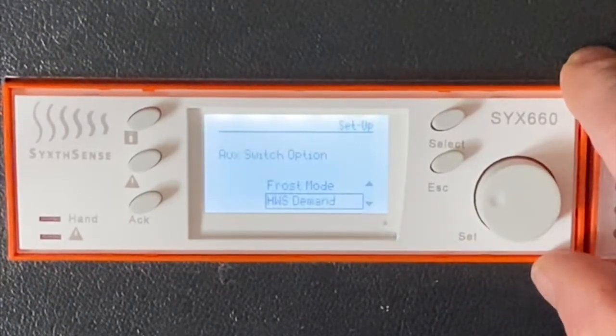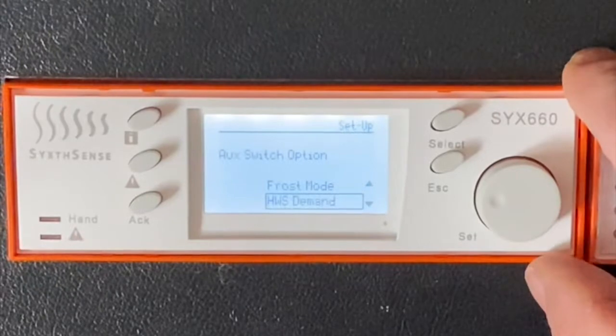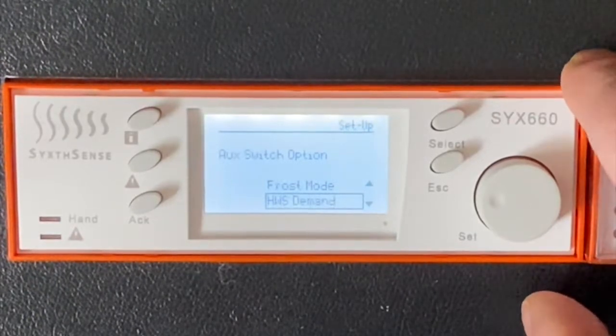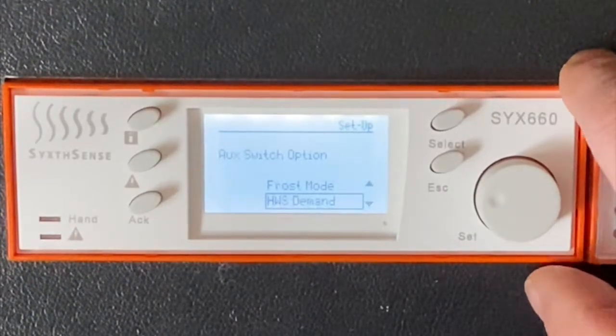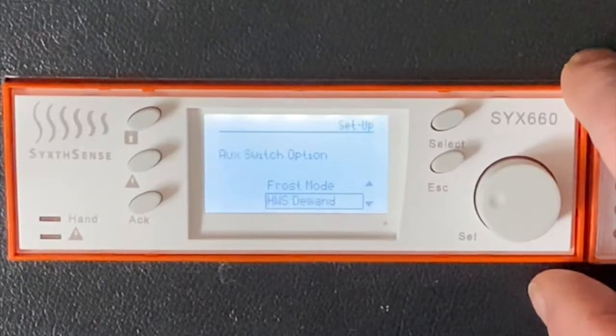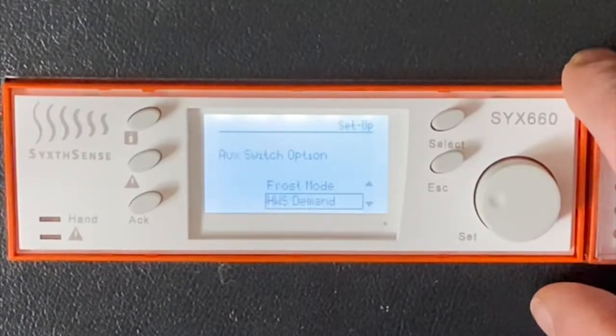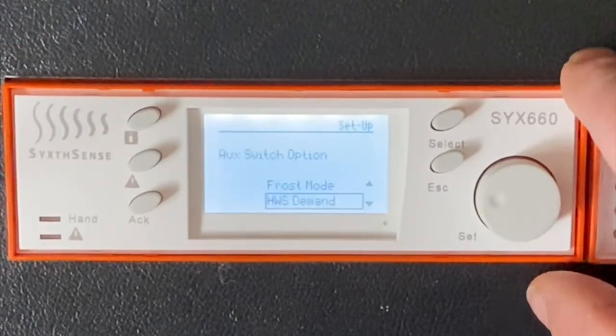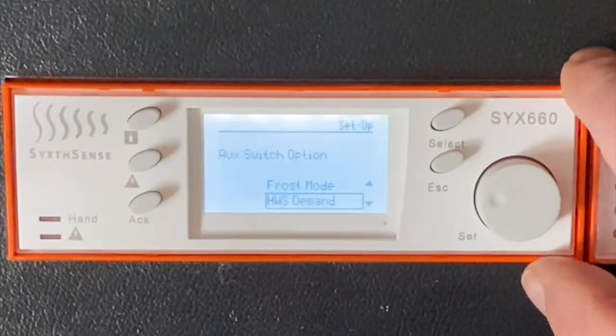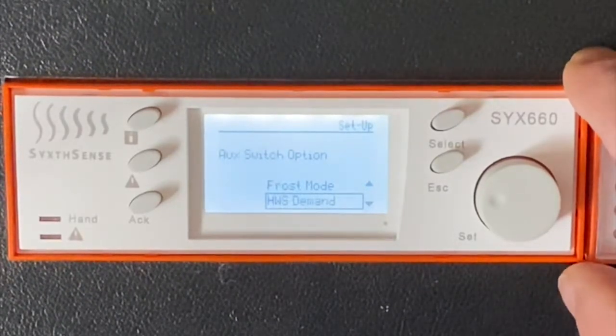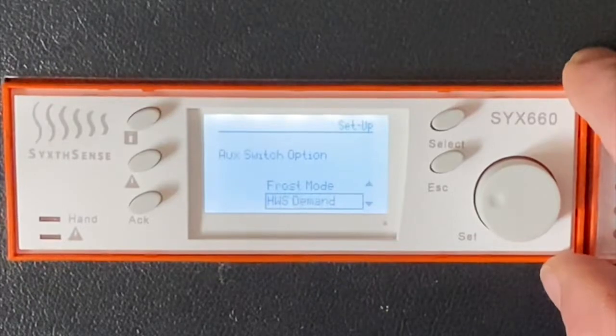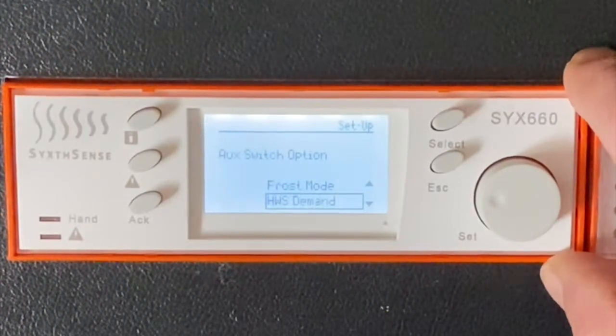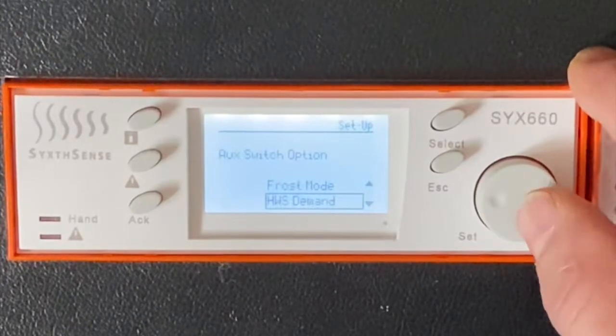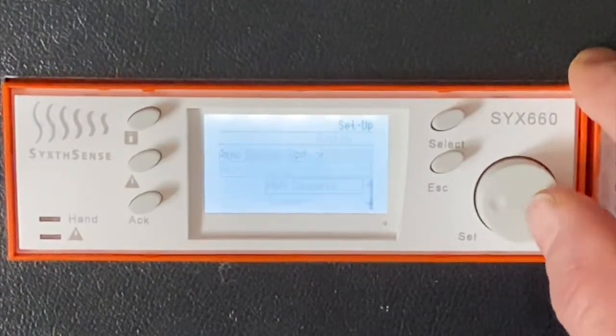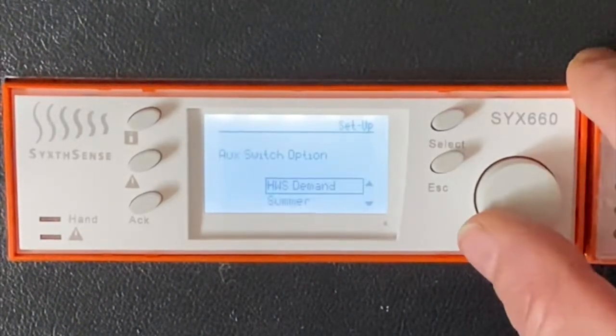Hot water demand is the option we're going to choose today. This is where we have a control circuit wired into the SYX controller as a volt-free contact, where we monitor the primary circuit demand, and once there is a demand proven by closing that contact, we then want to ramp up the boiler output so that it services the hot water demand. So I'm going to choose hot water demand shortly.